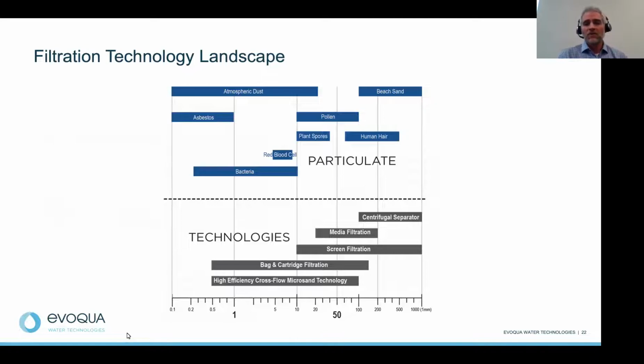So now, again, I mentioned it has great capability of very different micron degrees. I talked about centrifugal separators before, going to around 100 micron. Screen filters now have the capability of going all the way down to 10 micron. So now we have the capability of removing a lot more particulate in a cooling environment, right? Remember Gary mentioned earlier that cooling towers are really air scrubbers, bringing in a lot of different types of particulate and debris from the environment.